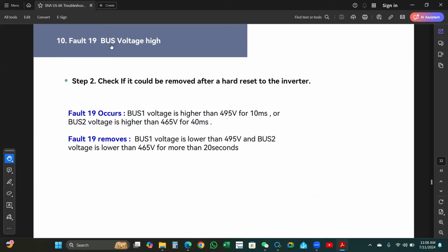Number 10, fault 19. Bus voltage high. Step 2. Check if it can be removed after a hard reset to the inverter. Fault 19 occurs when bus 1 voltage is higher than 495 volts for 10 milliseconds, or bus 2 voltage is higher than 465 volts for 40 milliseconds. Fault 19 removes when bus 1 voltage is lower than 495 volts and bus 2 voltage is lower than 465 volts for more than 20 seconds.